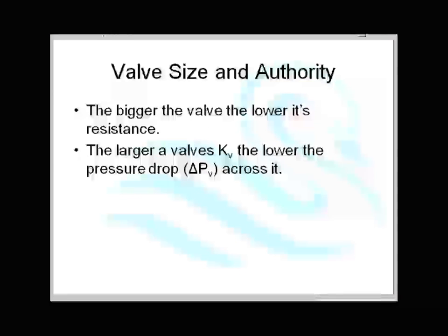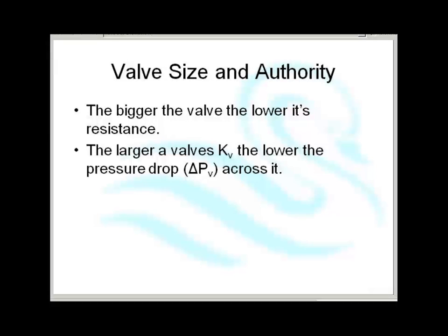Okay then. Now, valve sizing and authority, what this actually means. What we have to bear in mind is the bigger the valve, the lower its resistance. So bigger valves have got lower resistance. Now, larger kV, the valve size is its kV. So what that means is the bigger the valve kV, the less pressure is dropped across the valve.